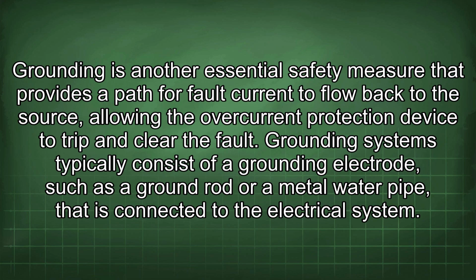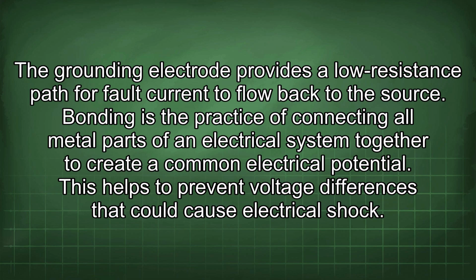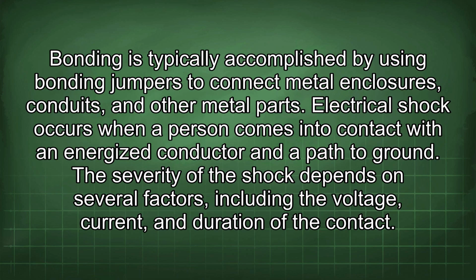Grounding systems typically consist of a grounding electrode, such as a ground rod or a metal water pipe that is connected to the electrical system. The grounding electrode provides a low-resistance path for fault current to flow back to the source. Bonding is the practice of connecting all metal parts of an electrical system together to create a common electrical potential. This helps to prevent voltage differences that could cause electrical shock. Bonding is typically accomplished by using bonding jumpers to connect metal enclosures, conduits, and other metal parts.